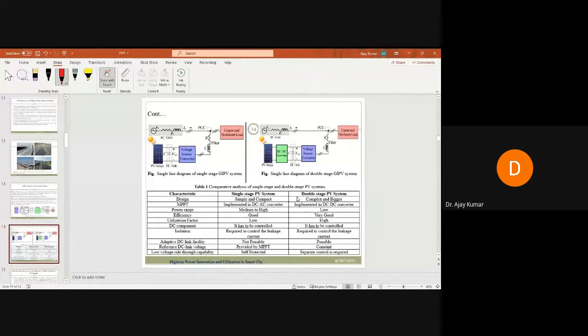If you want to talk about the single stage system, it is the simplest and most compact one, because only one power electronic device is there, and it is easy to control. But the issue is that two control algorithms must be implemented simultaneously: one for the solar photovoltaic system to extract maximum power, that is MPPT, implemented through the inverter, and another for the inverter control algorithm used to synchronize the converter with the grid at the point of common coupling, as seen in the first diagram on the left hand side.